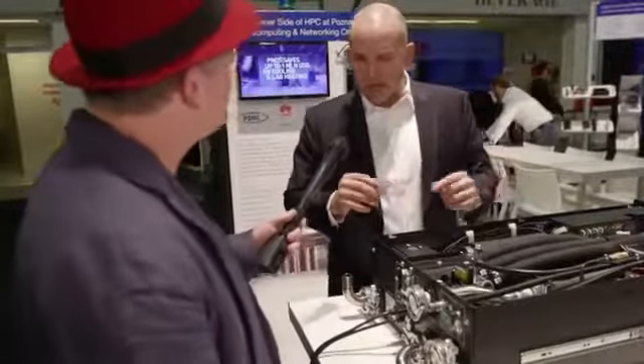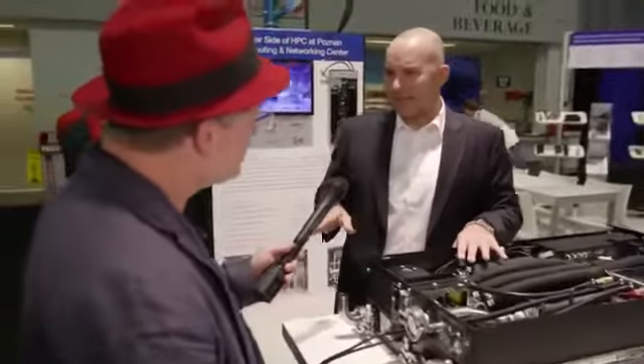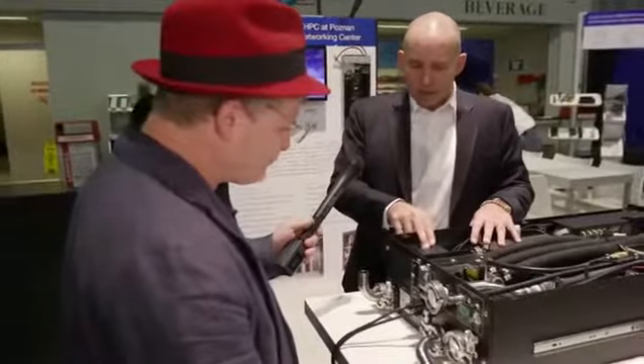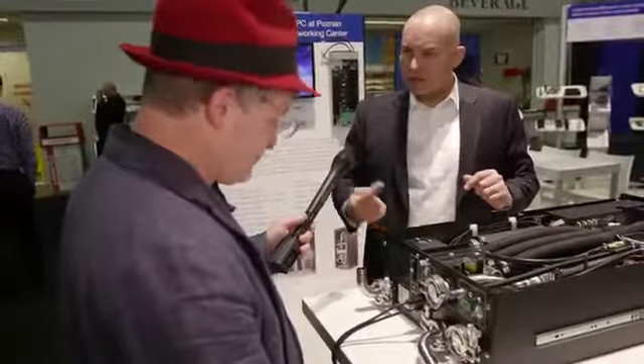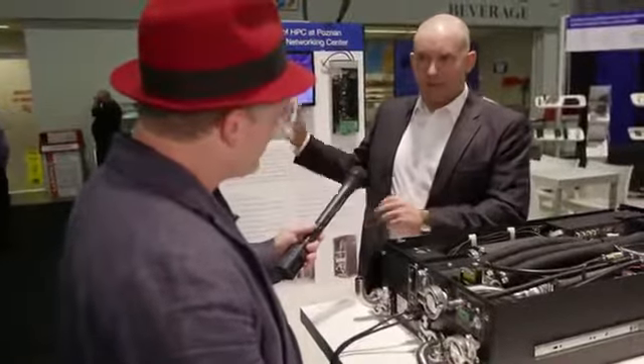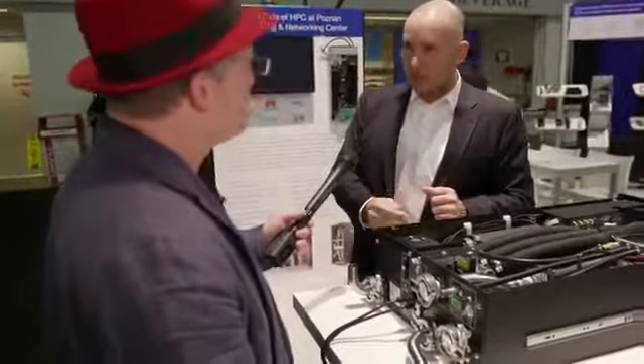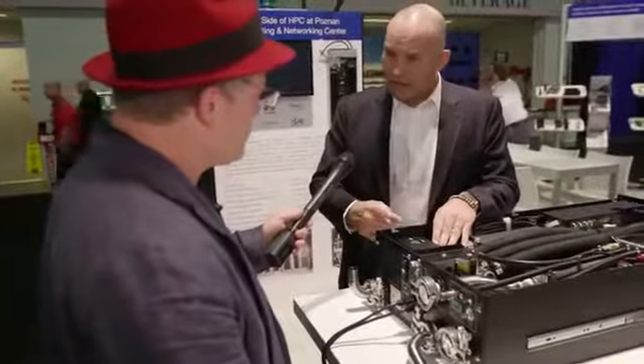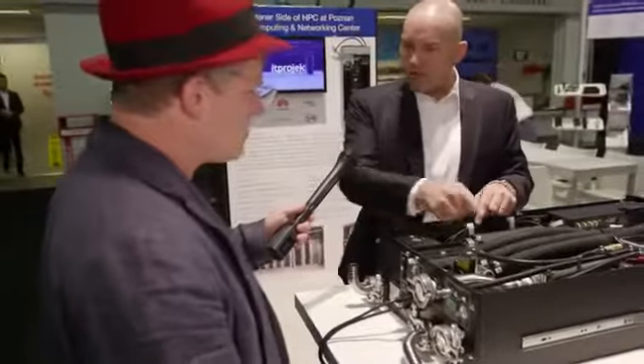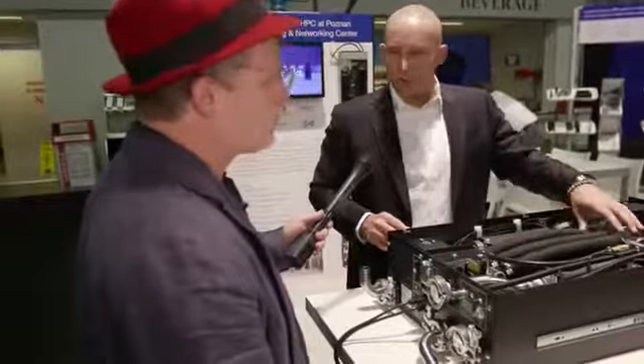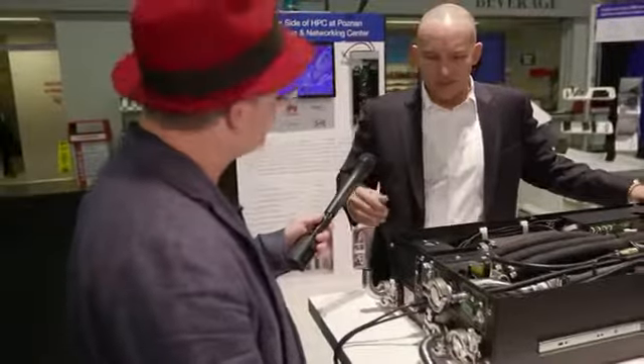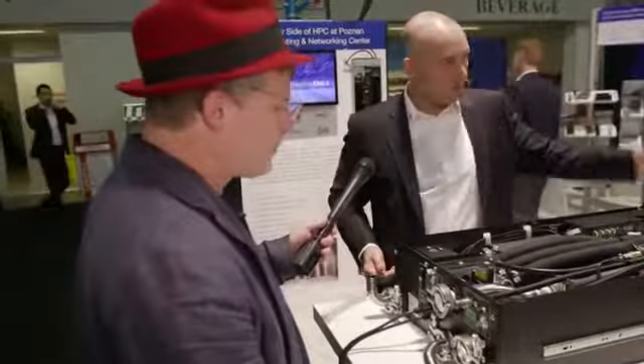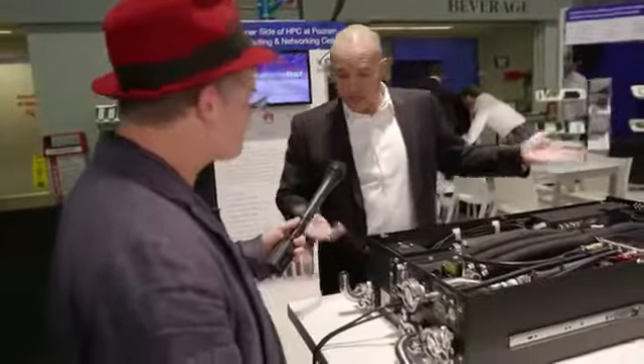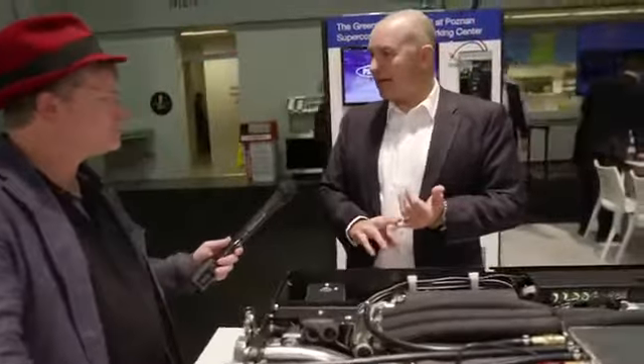So on the CHX40, we would actually just pinch off the flow if the water was too cold, right? So we protect against condensation. But with this, when we're dealing with much larger flow volumes, the facility guys prefer if they can have one constant flow going in and out. So we accept the same amount of water in and out, but if it's too cold, we just divert the water that we don't need so that we don't overcool the secondary coolant, so that we don't have condensation and rain starting to happen inside the rack. The control system, obviously, is still reporting in all of the various different formats that everybody wants.